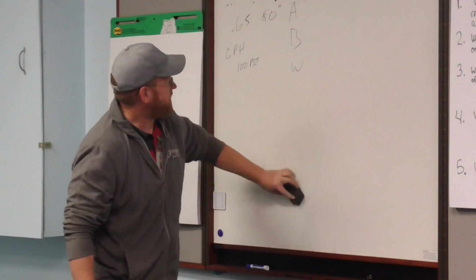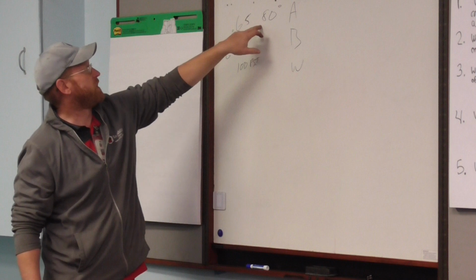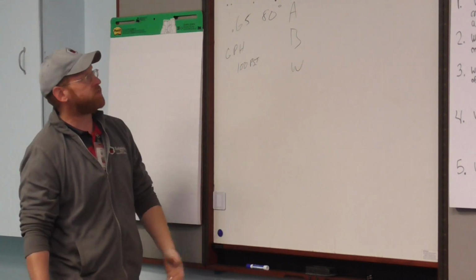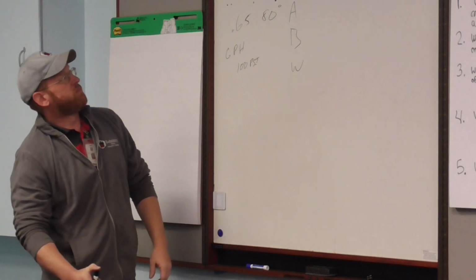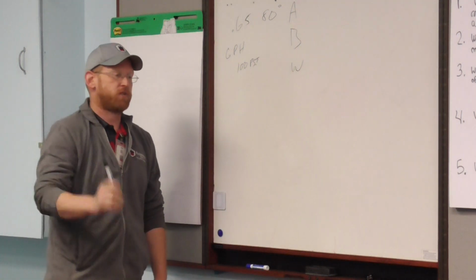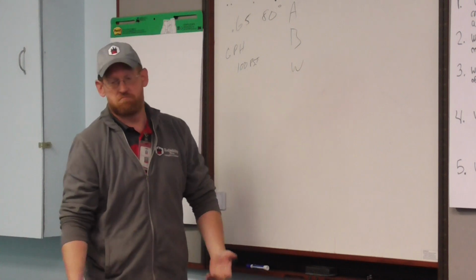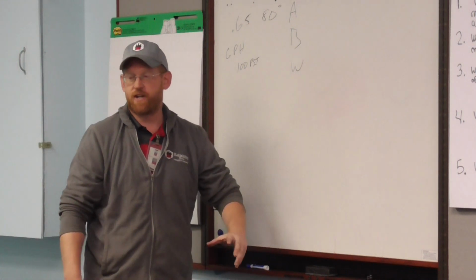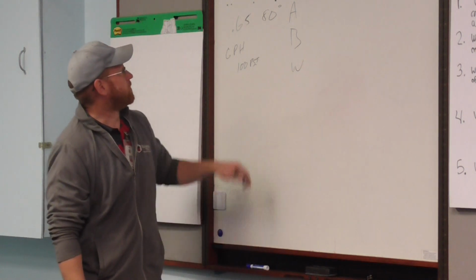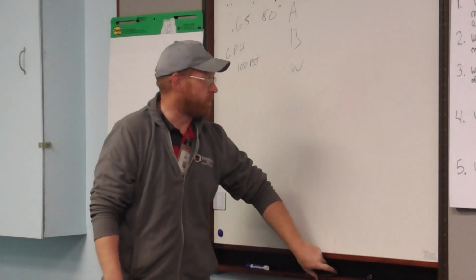If you change this by 10 degrees, like if you only have a .65 70 and stick it in there, it's not ideal, but it may be close enough. If you change it to a .75, you have to adjust the air, it's gonna spray way too much fuel. Put it to a .45 or .55, cut the oil down, you have to cut the air down to match it. The .65 is the most important number.